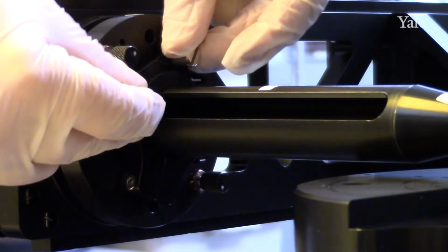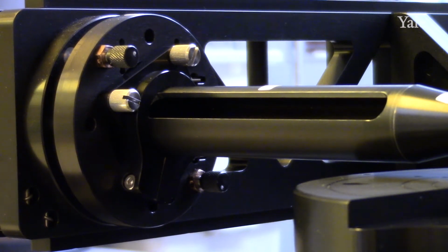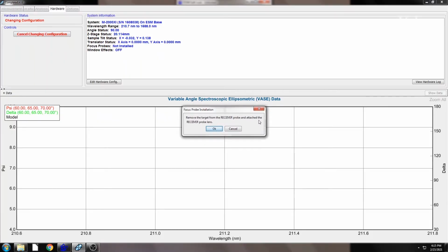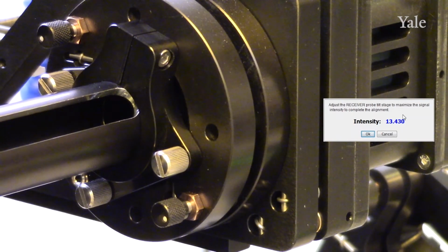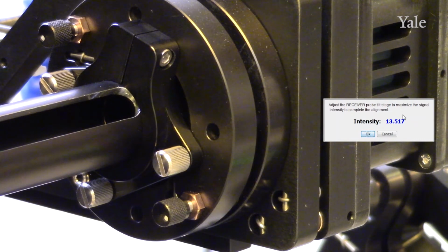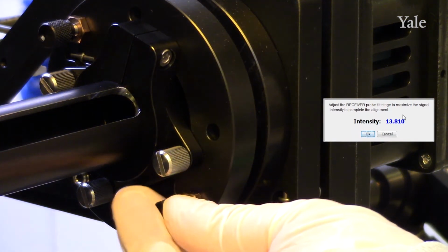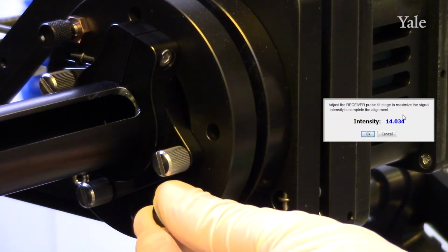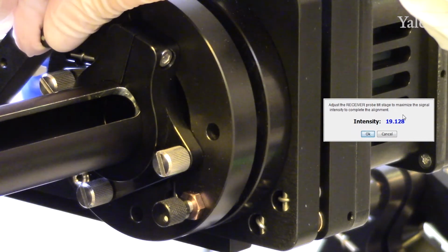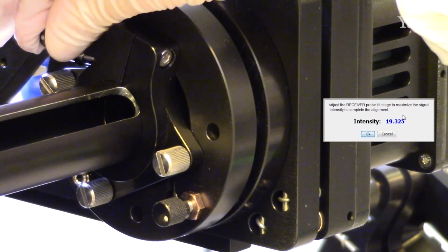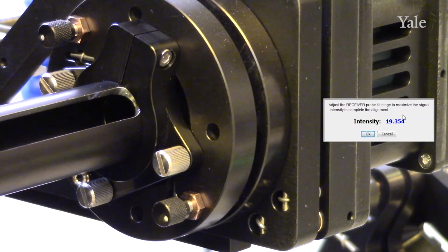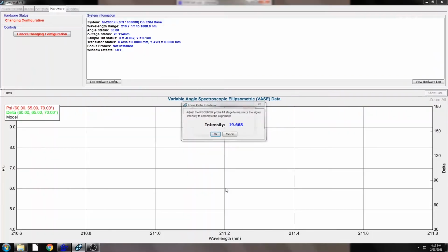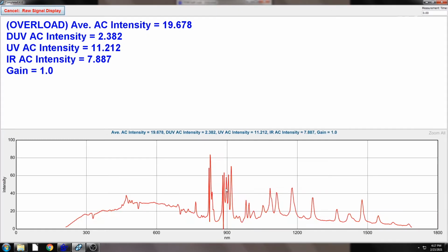Next, the software will prompt you to remove the receiver target and attach the lens. This instruction can be ignored as we started with the lens attached. Next, we will adjust the receiver probe tilt in order to maximize intensity. While watching the intensity value on the screen, first adjust the X alignment until you get a local maximum. Then, fine-tune it using the Y alignment. Here we can see our max intensity is 19.3. Once the X and Y tilt is set, press OK so the delta offset can be measured. Once this step is completed, you are now ready to perform measurements using the focus probes.